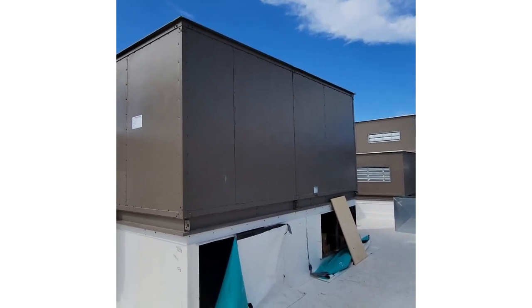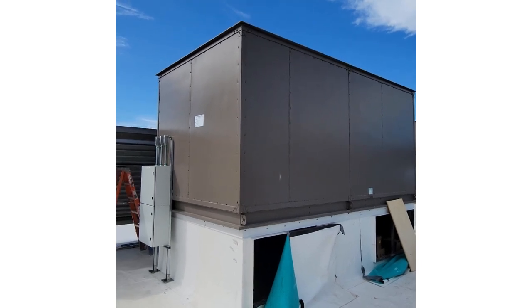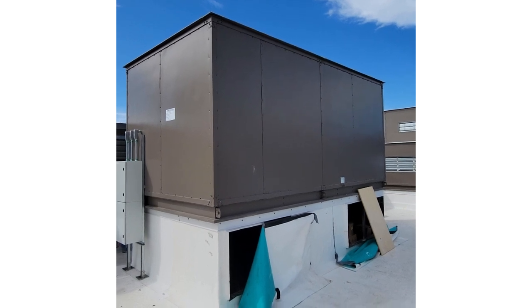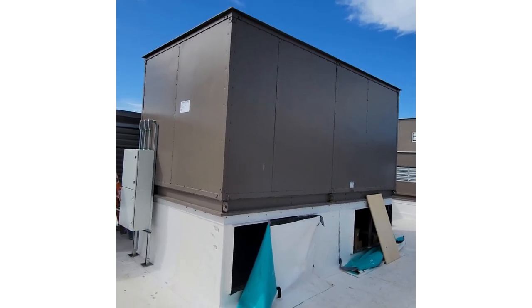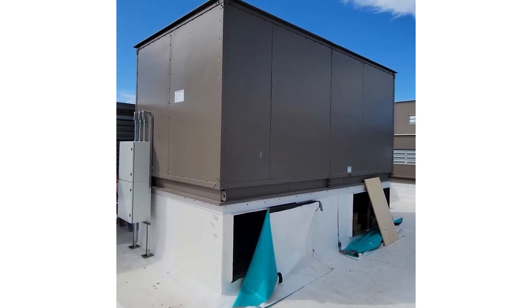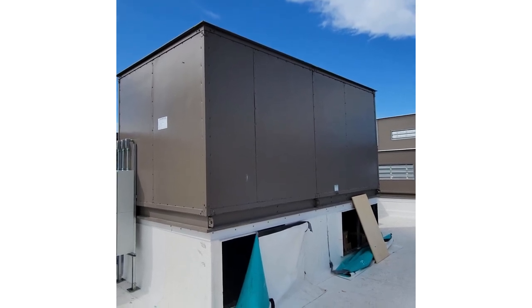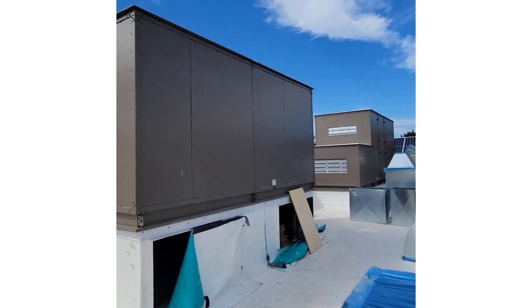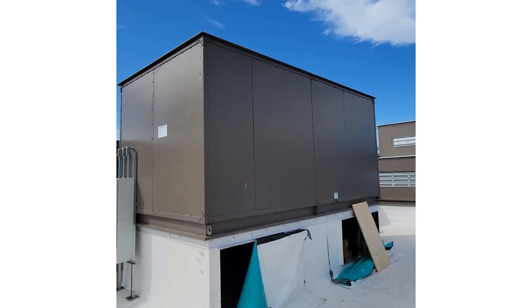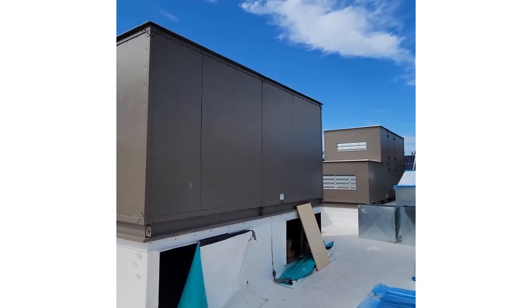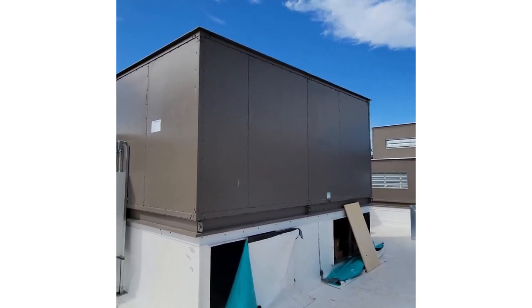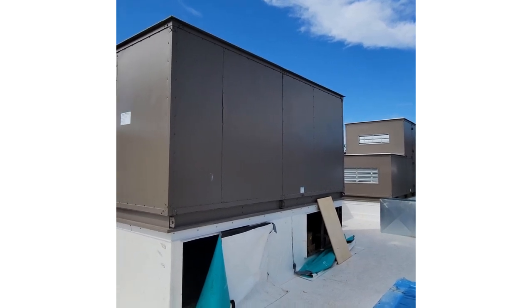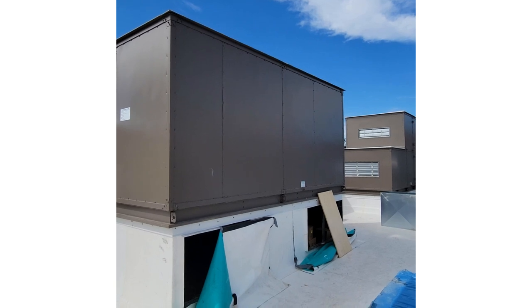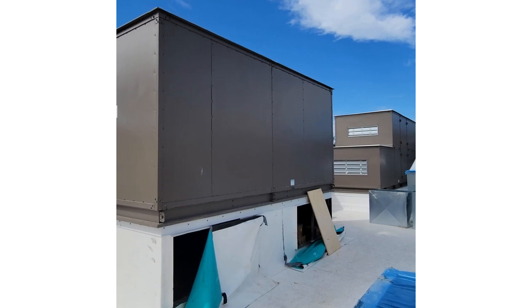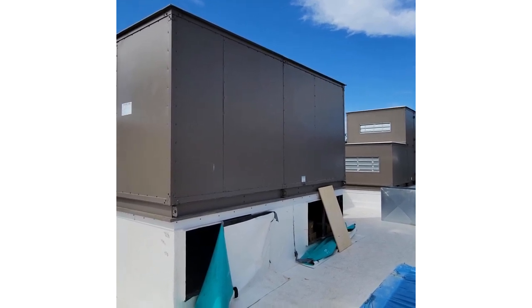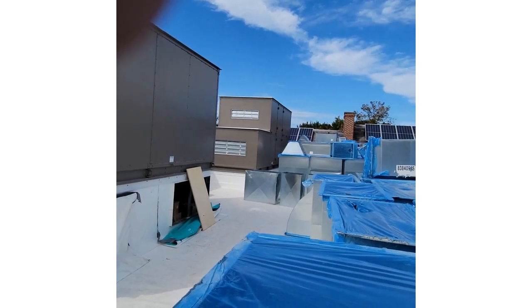The difference between an air handling unit and a rooftop unit is that rooftop units had all the components that did the air conditioning and some of the heating—compressors, the freon cycle, electric power, controllers, and all that. None of that's in these units. They're much simpler, which is one reason we have a much longer life expectancy, approximately twice that of the rooftop units, since they're rough and tough mechanical systems, nothing sophisticated. All that's down in the sub-basement with the ground source heat pumps, protected from the environment, so it should last much longer than our previous system.